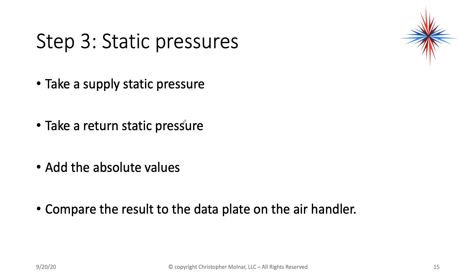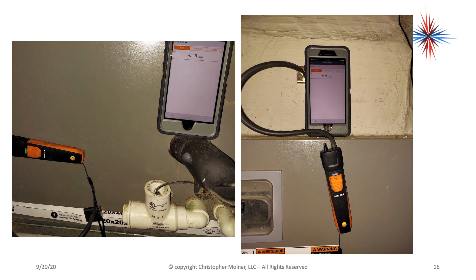Now we want to take static supply pressures, static return pressure, and then add the absolute values. Static pressure is the outward pressure — it's not velocity pressure, it's not the pressure of the air moving. It's the outward pressure on the ductwork. We drop the signs because our supply is going to be positive and return is going to be negative, then we add them together and compare that to the data plate on the air handler. Here's an example.